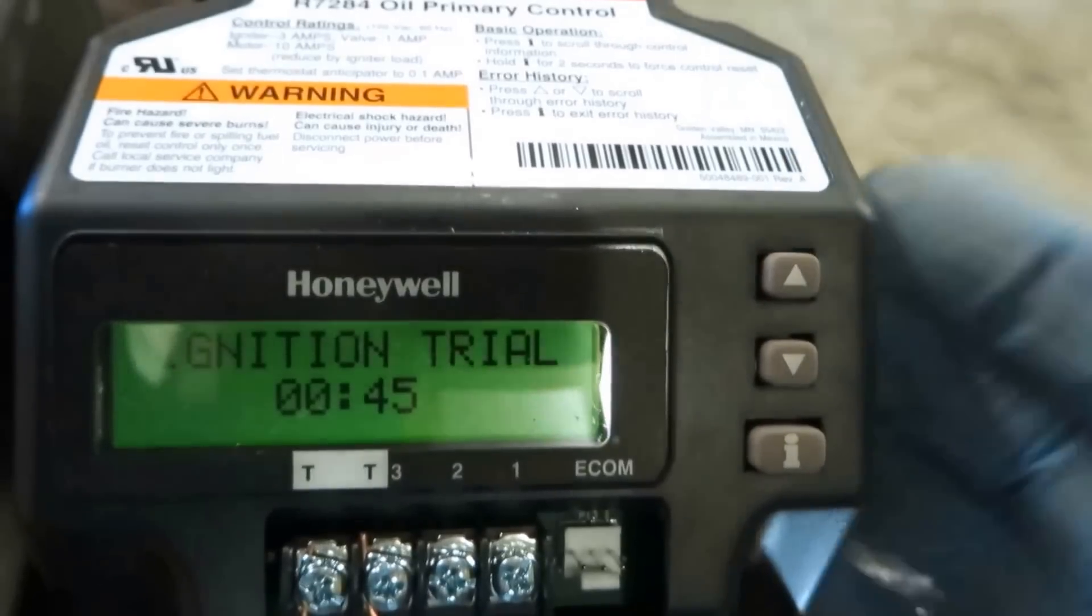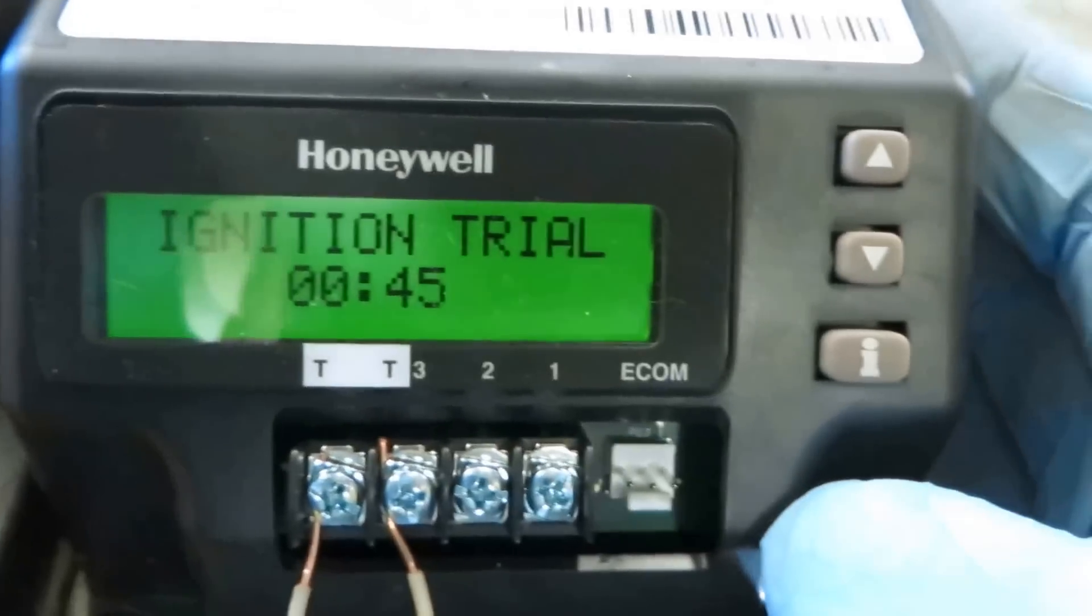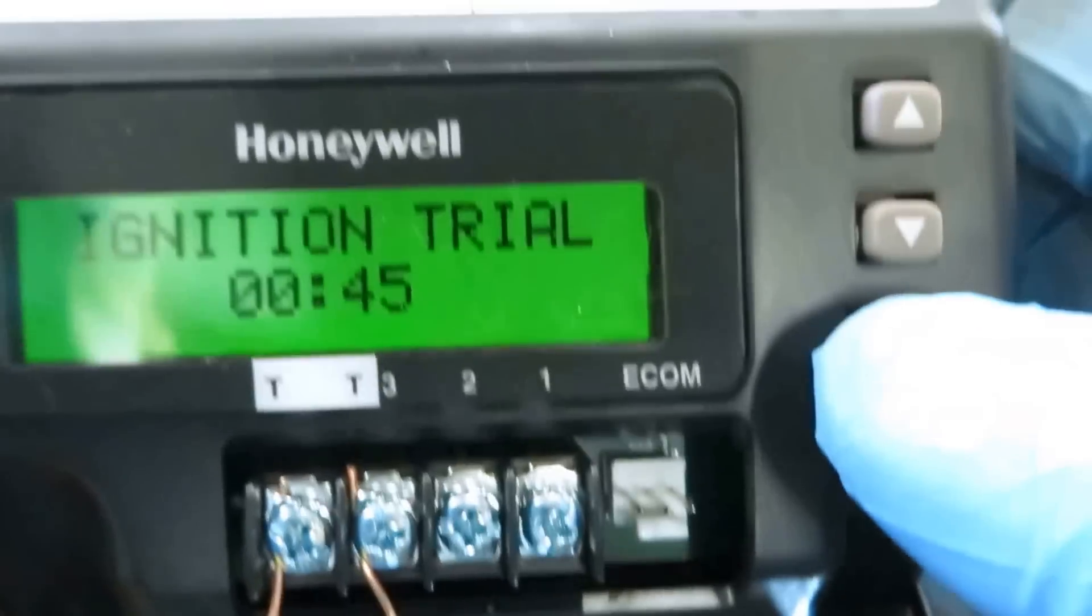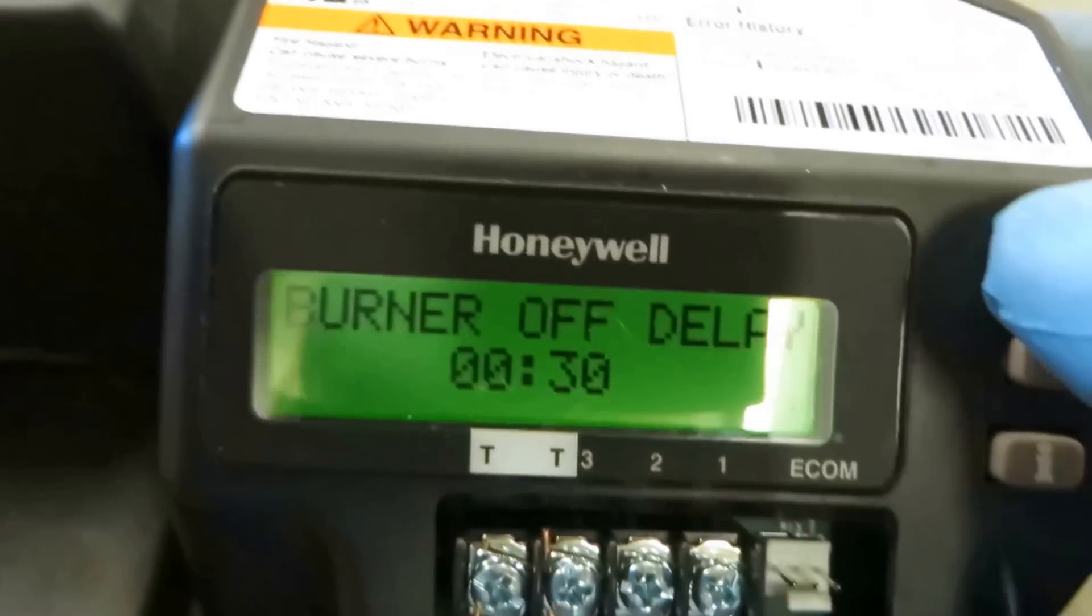Ignition trial, I like a 45 second. You can do 15, 30, 45 seconds. I like a longer. Burner off delay, I got 30 seconds.